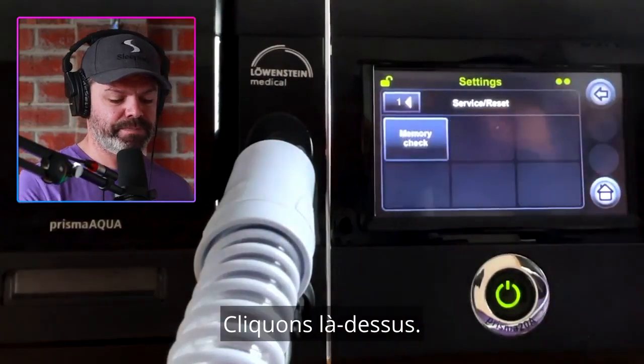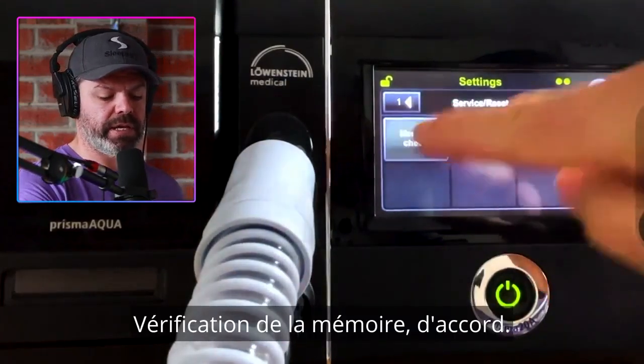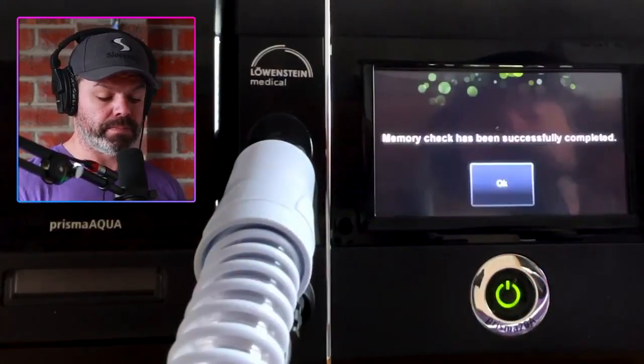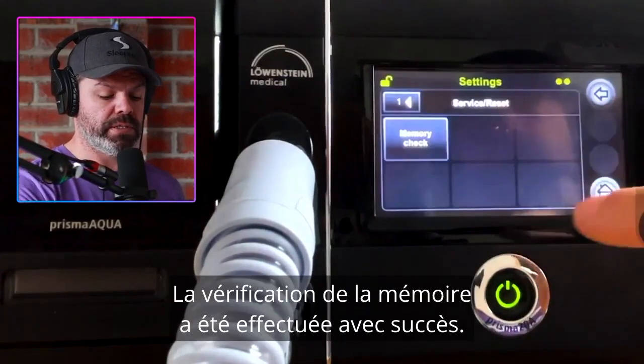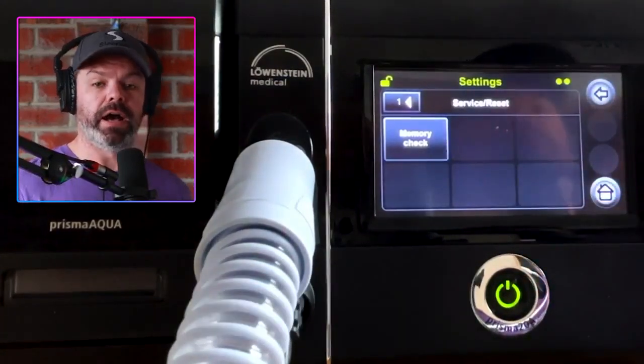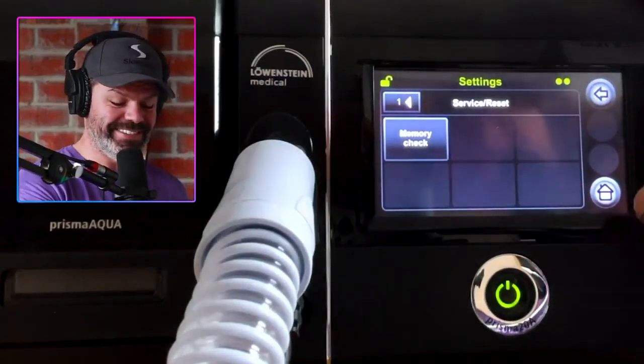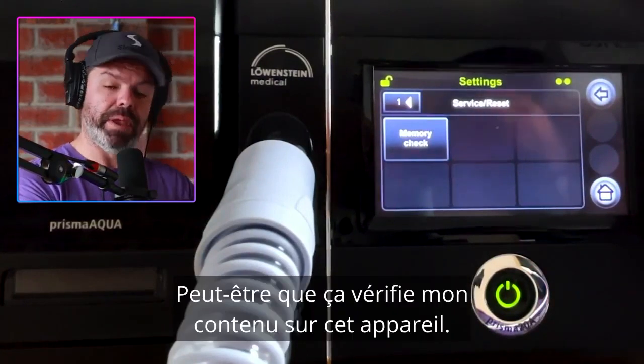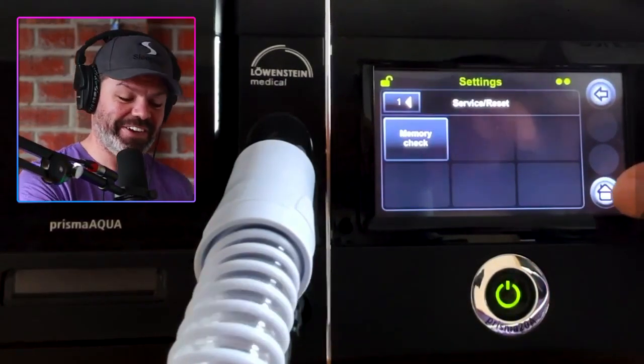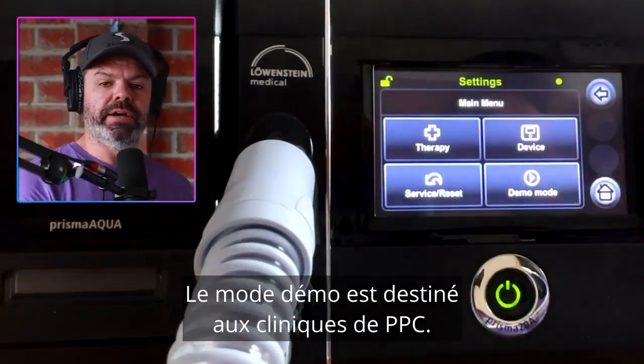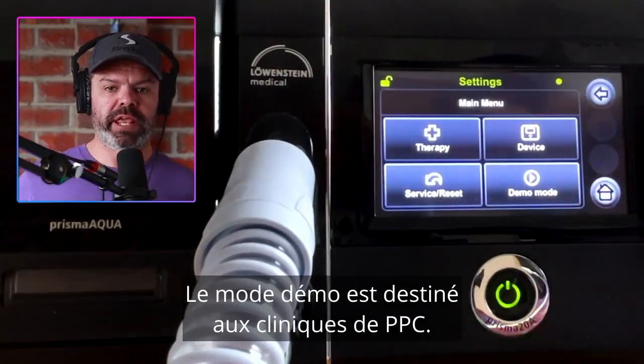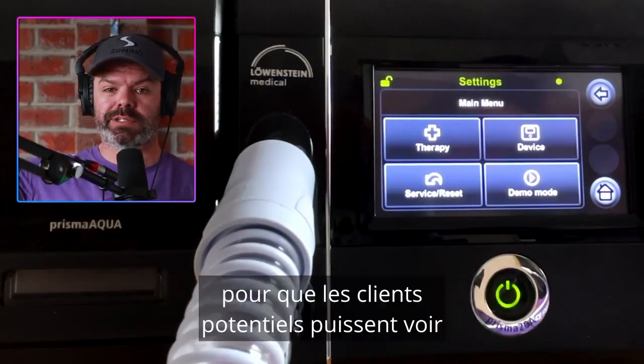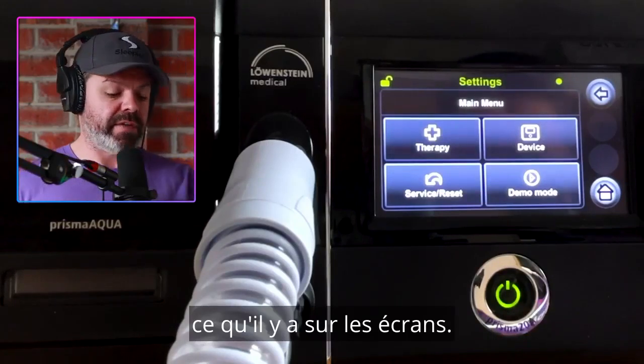There's a memory check — let's see how much memory is on this device. Memory check has been successfully completed. I assume it's checking the storage capacity. And demo mode here is for CPAP clinics — they can put the device on a shelf, click demo mode, and it runs through different screens so potential customers can see what's on them.